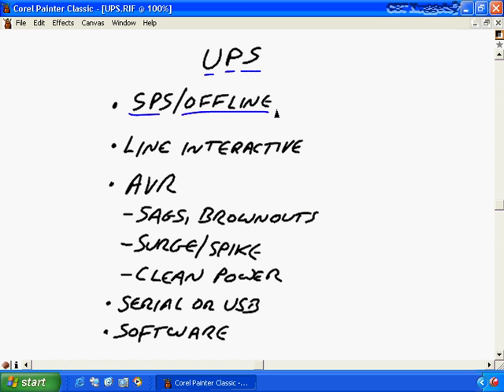There are a couple of different types of UPSs. One is a standby power supply, also known as an offline power supply. With this one, the UPS is really just a conduit for electricity—it goes from your wall outlet to the UPS and then out to your PC, not working much differently than a power strip or surge suppressor. However, if the power goes out, there's about a 10 millisecond lag between the time the power goes out and the offline UPS comes online and starts supplying battery power. Most power supplies inside computers can bridge that 10 millisecond gap because of the capacitors in there, but personally I'm still not comfortable with it. I'd rather have more immediate power, even though 10 milliseconds is really short.